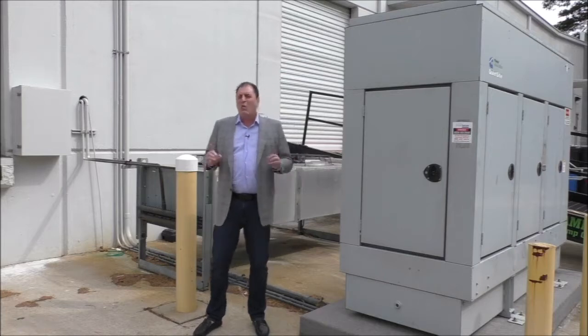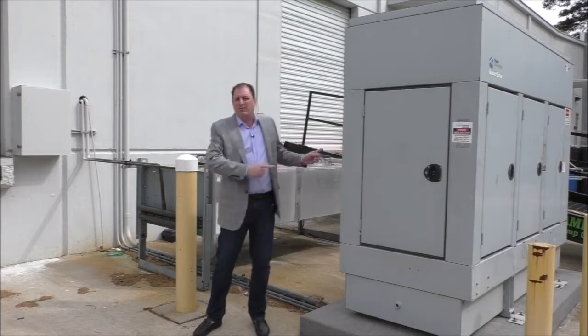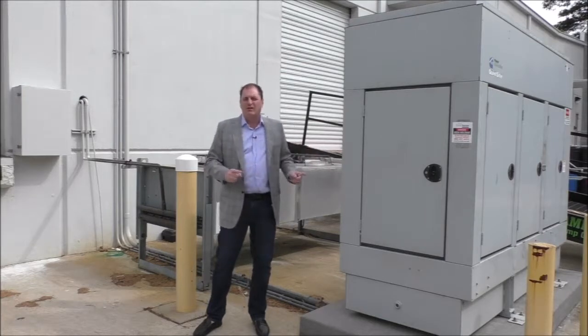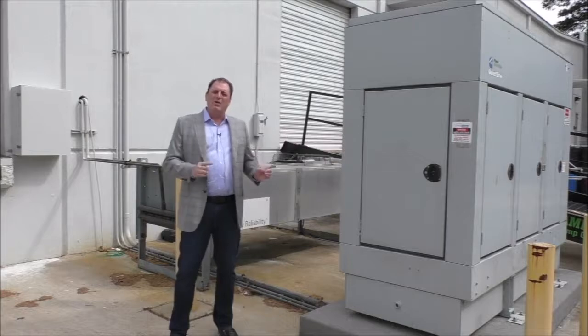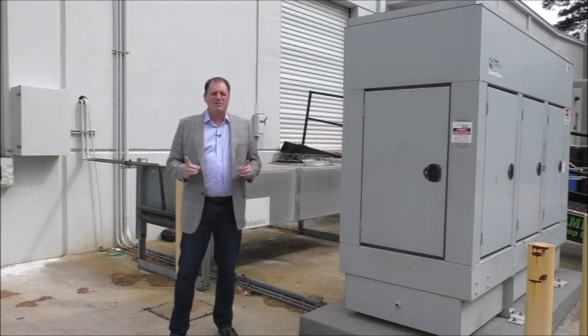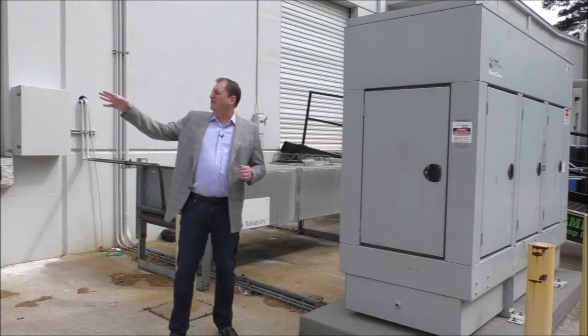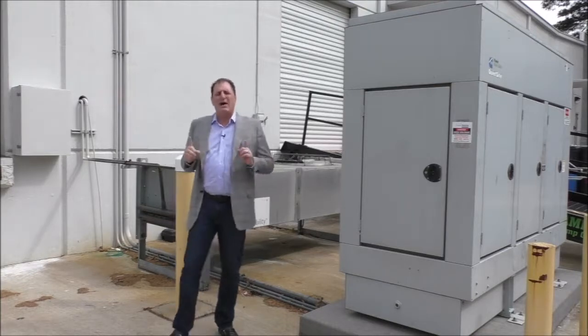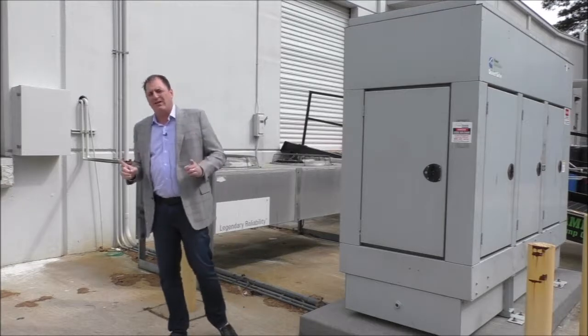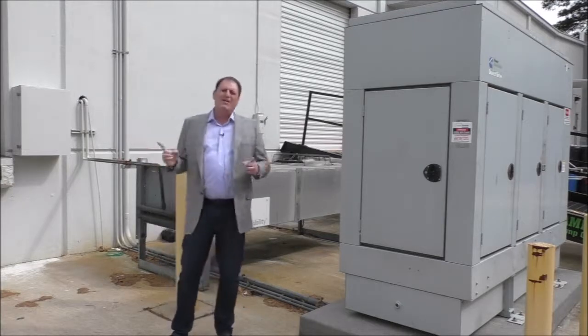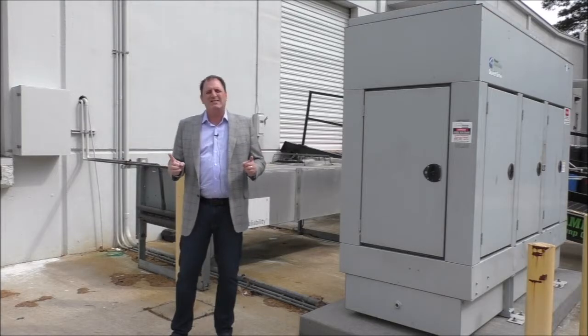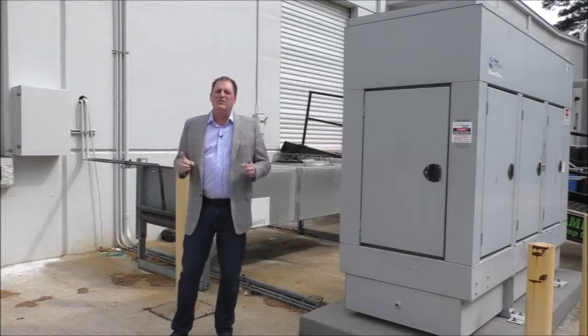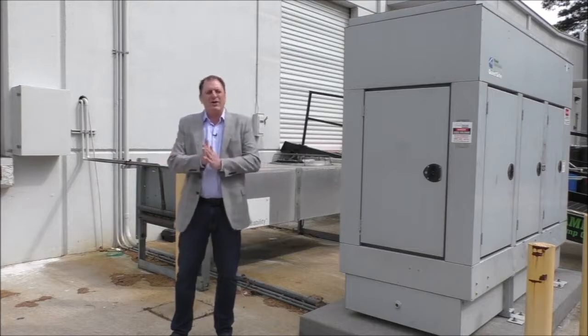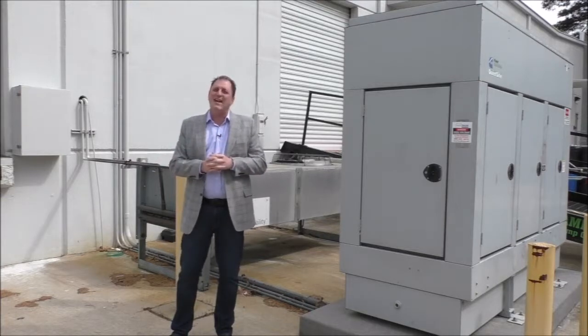So again, why is the UPS the heartbeat of the data center when it's the generator that can power it for as long as you need when the power goes off? And that's because when the power goes off, before the generator comes on, there is a delay. Let me demonstrate. Cut the power. We don't have AC power right now to our office or our data center, and yet the lights are on in there, and that is because right now the UPS is carrying the load. It will continue to do so until the generator comes on. Let's see how long that takes.